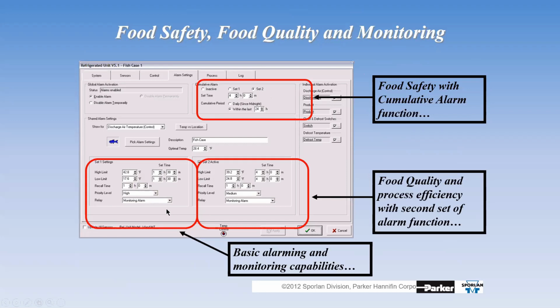The reason we do this is because of what happens with other modalities - I learned this by watching bad technicians. If I've got a case that's always a problem in the store, how do I solve it? I go in, and instead of the alarm point being at 42, I jack it up to 50 degrees. Now I never get an alarm, and you think I did my job well, but no - I just put a Band-Aid over the problem.